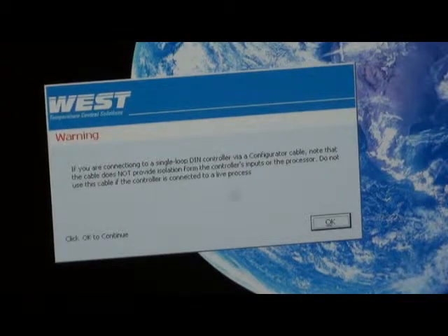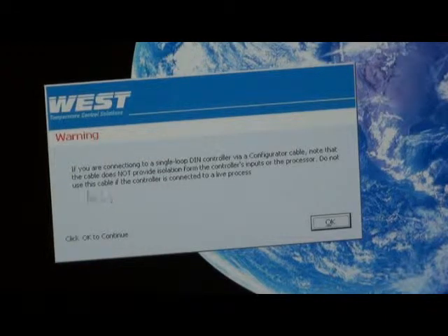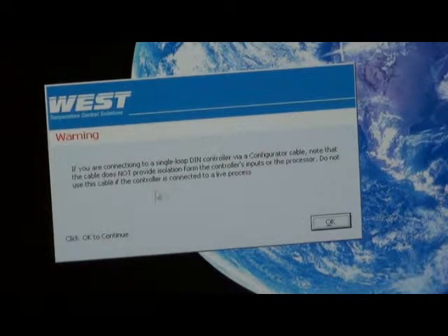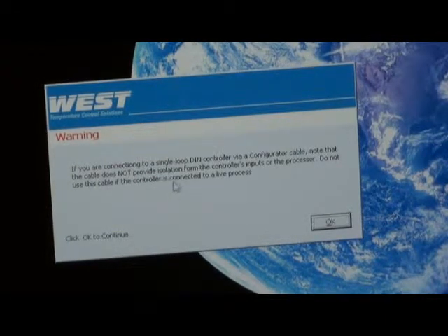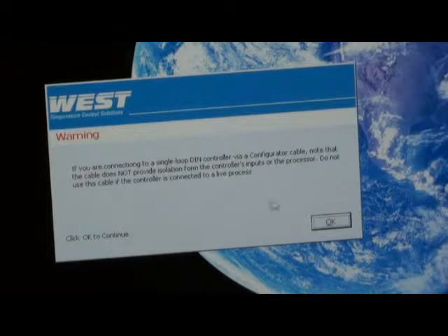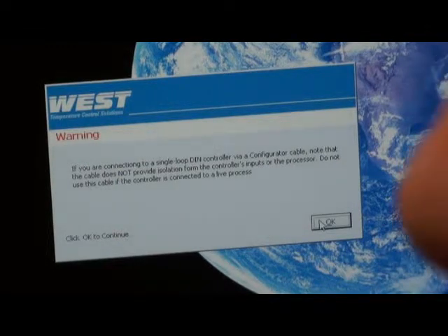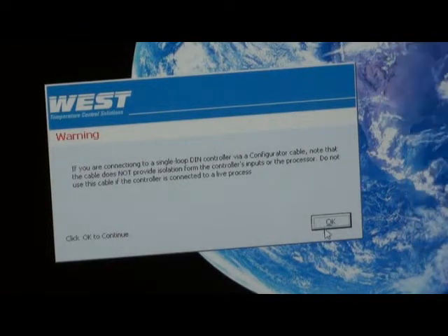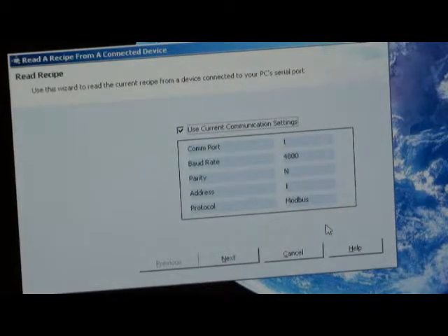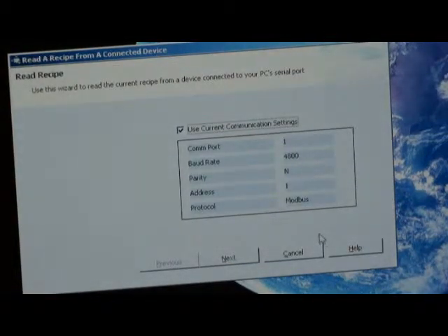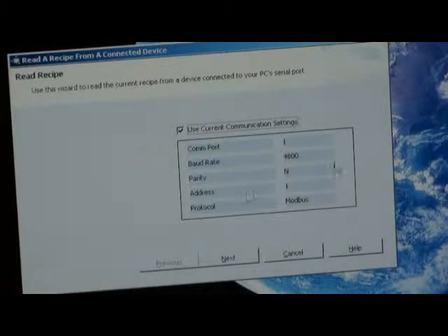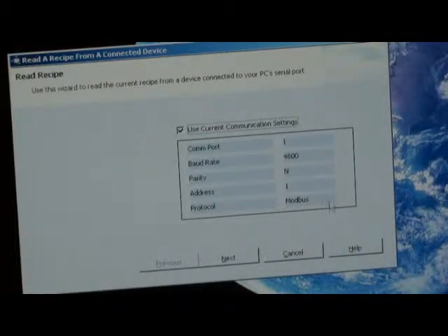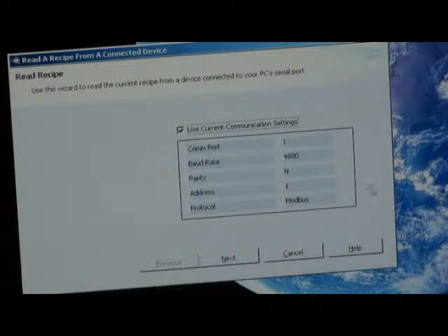A warning here: don't try and use this cable if the controller is connected to a live process. So disconnect from a live process first of all. These are the communication settings: comms port, the baud rate, parity, address and protocol. All standard defaults.